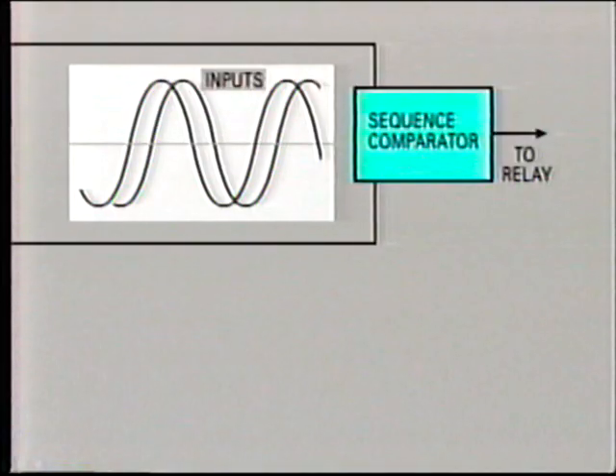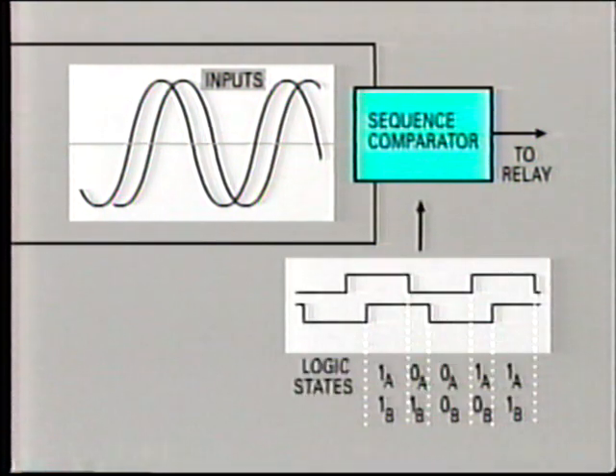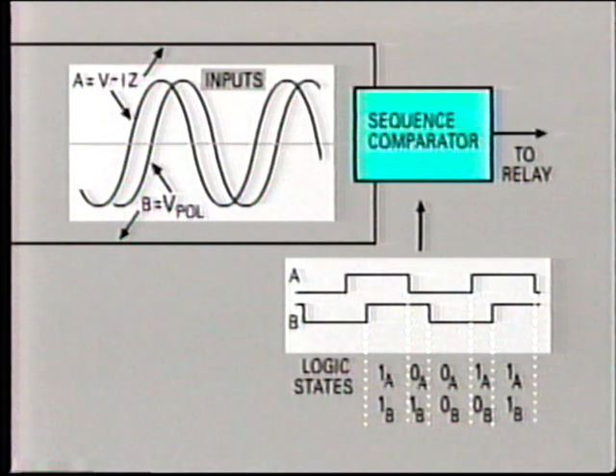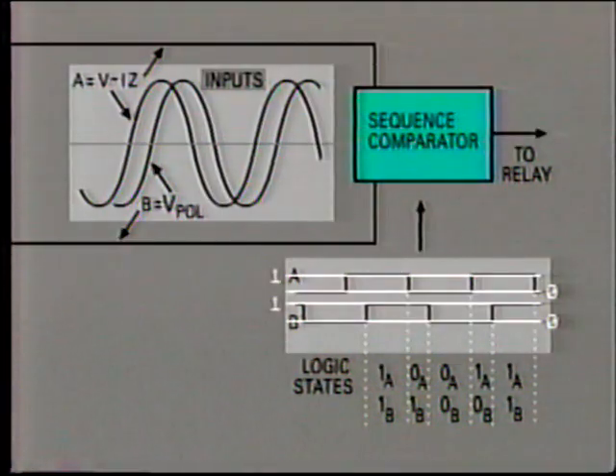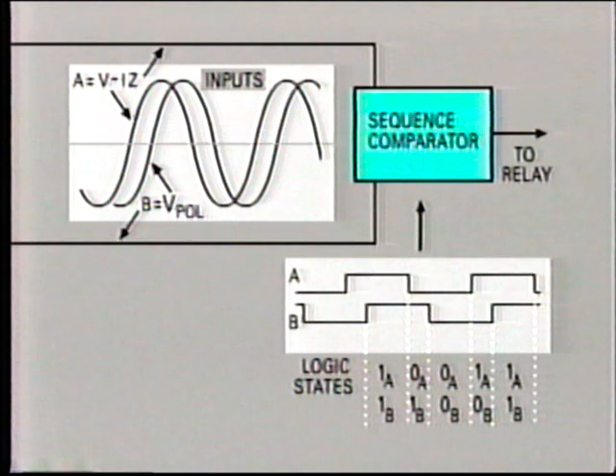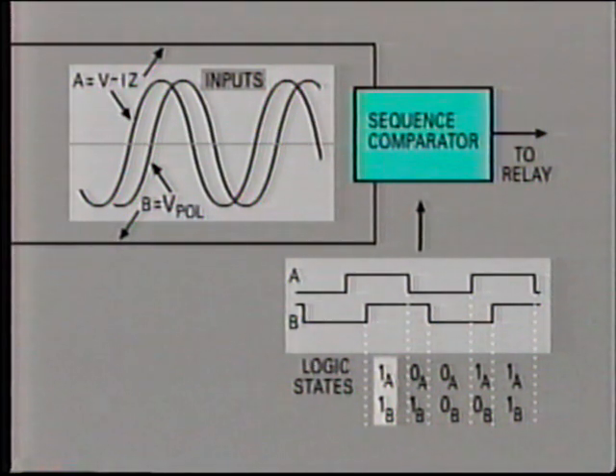How is this done? Well, these two sinusoidal quantities are fed into the sequence comparator, which converts them to square waves and then compares the logic sequence. For simplicity, let's call V minus IZ A and the polarizing voltage B. The square wave has only two values, high and low, represented by 1 and 0, respectively. For an external fault where A leads, the signal sequence will read 1 sub A, 1 sub B, 0 sub A, 1 sub B, 0 sub A, 0 sub B, 1 sub A, 0 sub B, 1 sub A, 1 sub B.